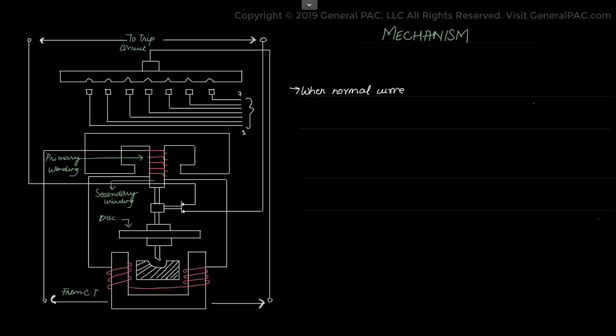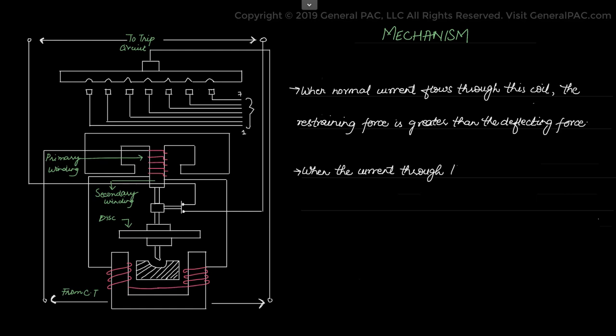How does the mechanism work for an overcurrent relay? This relay consists of a current coil and a disk which is free to rotate between the poles of two magnets. When a normal current flows through this coil, the magnetic effect generated by the coil on the disk is not sufficient to move the moving element of the relay.